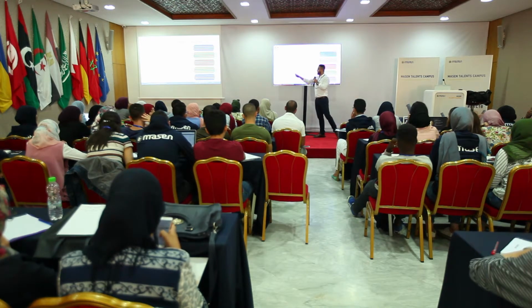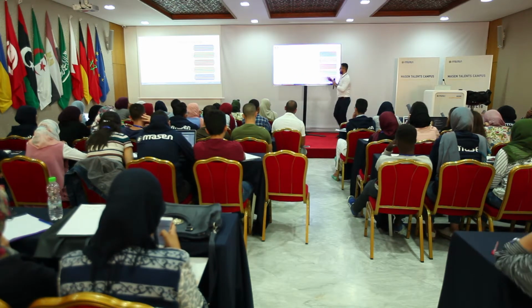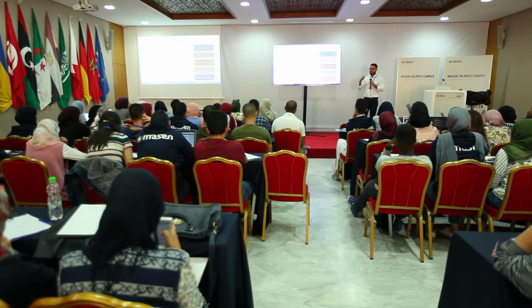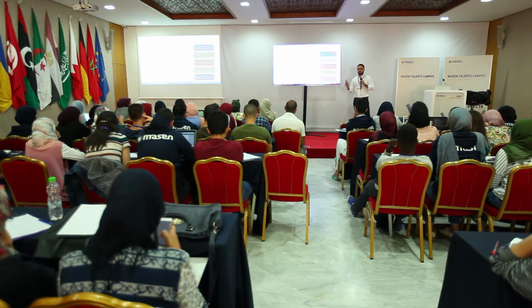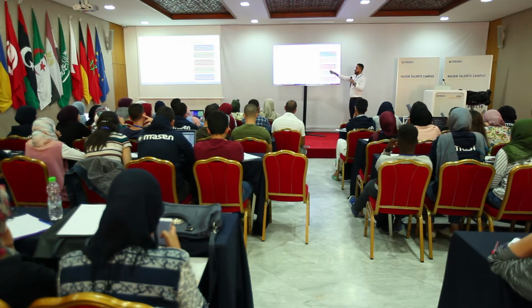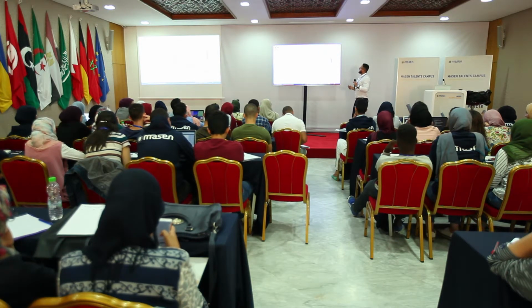Now, what you see below is my actual power plant performance based on this. So this is the energy collected. What I see here on the green one is the energy from the receiver to my hot tank. So the energy that is being stored, from the receiver to the hot tank. The blue line is my storage tank. It's a percentage of how full it is.